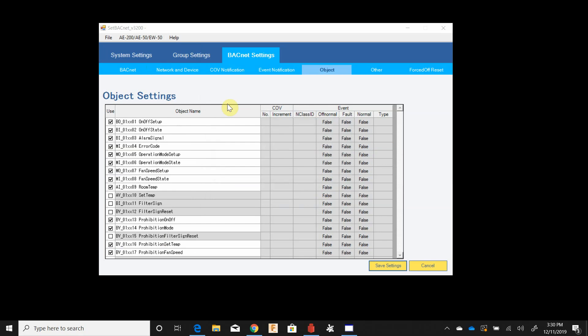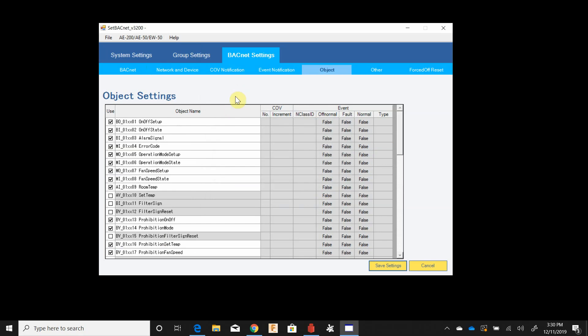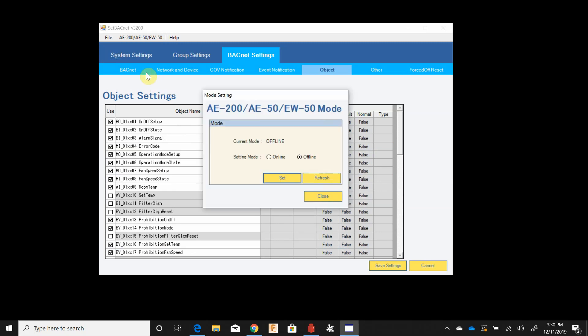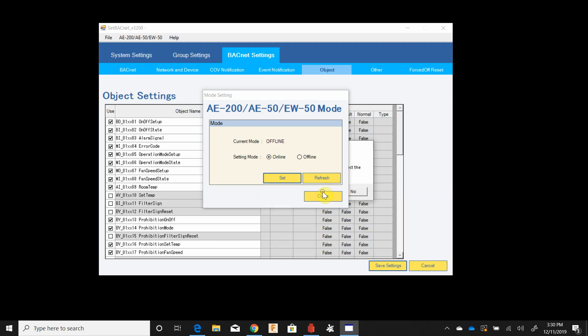So after the settings are sent we need to go to mode setting and put it back into online mode. Once you set this it will take a while, the AE-200 will search for devices, do some other stuff, and then it will shut down and power back up. So hit the set button, you'll walk away for 5 to 10 minutes, come back and open this back up and hit refresh. So I'm going to go ahead and set, it's going to give me a warning that it will automatically restart the AE-200. I'm going to press yes and I'm going to go ahead and pause the video and come back after this has reset.